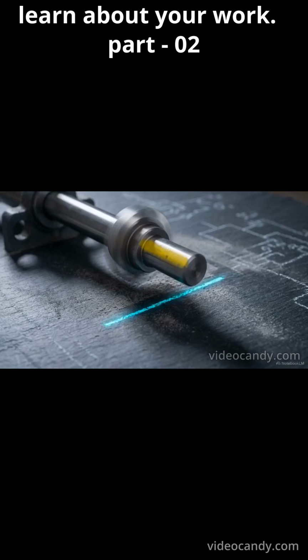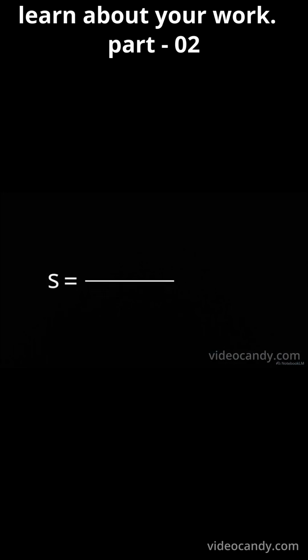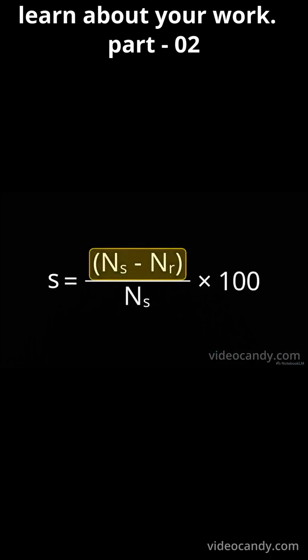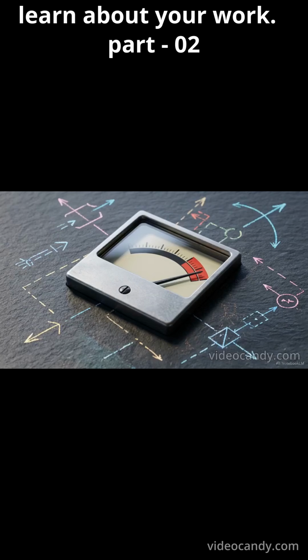Reaching synchronous speed is physically impossible under load. If the motor ever caught up to the field, it would instantly lose power and decelerate. This mandatory physical lag between the speed of the magnetic field and the mechanical speed of the rotor is known as slip. Engineers calculate this lag as a percentage, comparing the synchronous speed to the actual rotor speed.